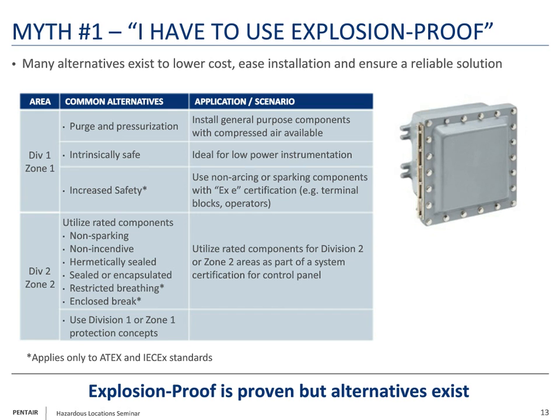In Division 2, Zone 2 areas, you can use rated non-arcing, non-sparking, non-incendive components, and then use them with a Type 4 or 4X or IP66 certified enclosure. Again, just different alternatives that would lower the cost, ease installation, and help ensure some reliability. If you look at a Division 2 application with a drive, you could always use a purge system to install that drive in that area, and then you can use cooling if you wanted to help keep that product reliable over a long time.